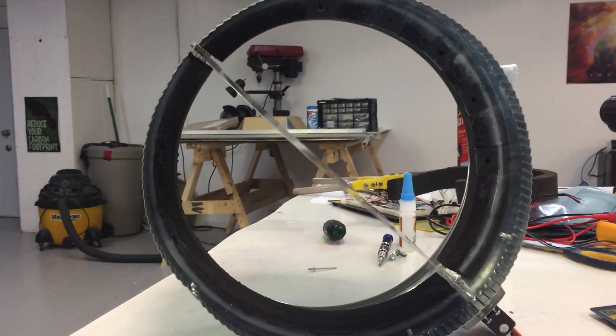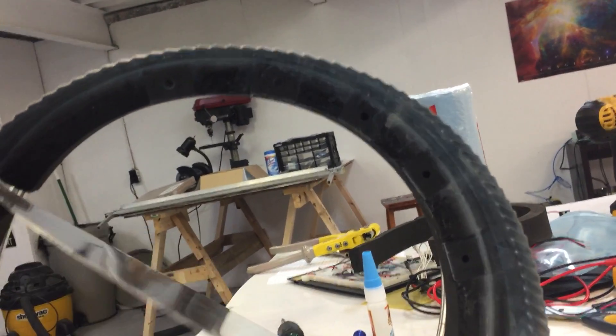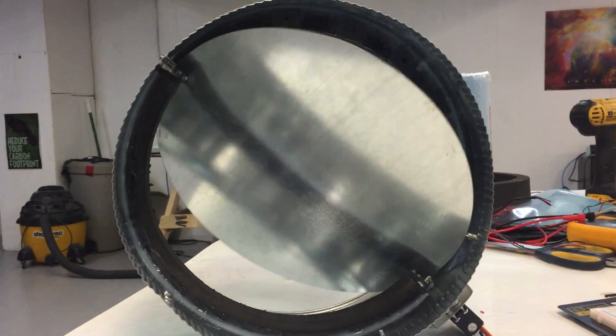What's unique about this damper design is that we've actually used magnets in order to help create the proper seal when it closes. You can see the 5 magnets along the rim there. When the damper gets near the closed position, the 5 magnets attract the galvanized steel plate and create a tight seal around the rim of the duct, making it a very airtight seal.